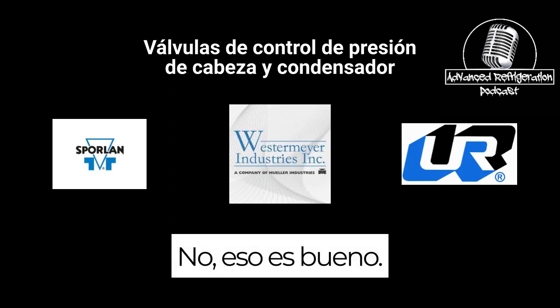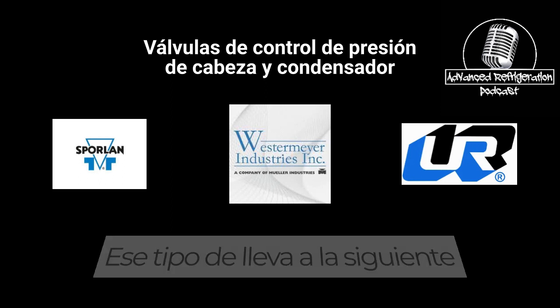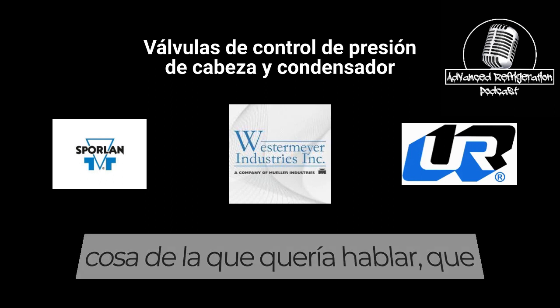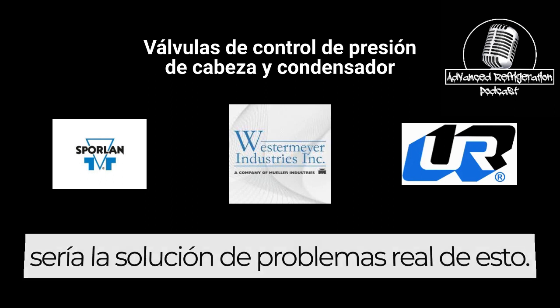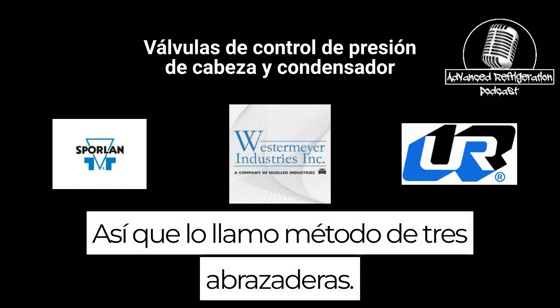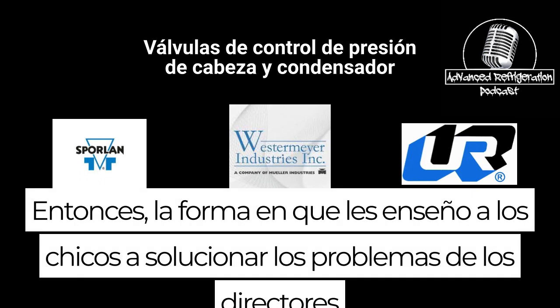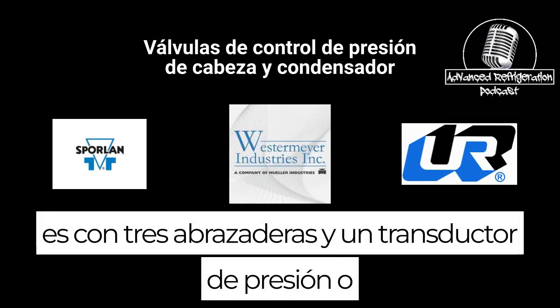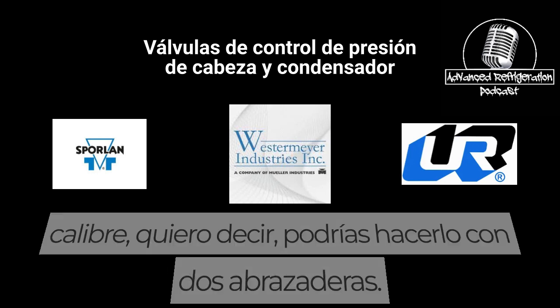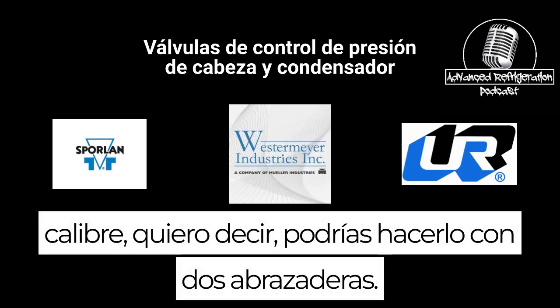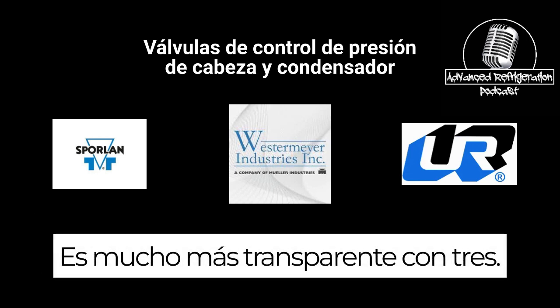No, that's good. That kind of leads into the next thing I wanted to talk about, which would be the actual troubleshooting of this. So I typically call it the 3-clamp method. The way I teach guys to troubleshoot headmasters is with 3 clamps and a pressure transducer or a gauge. I mean, you could do it with 2 clamps. It's a lot more transparent with 3.